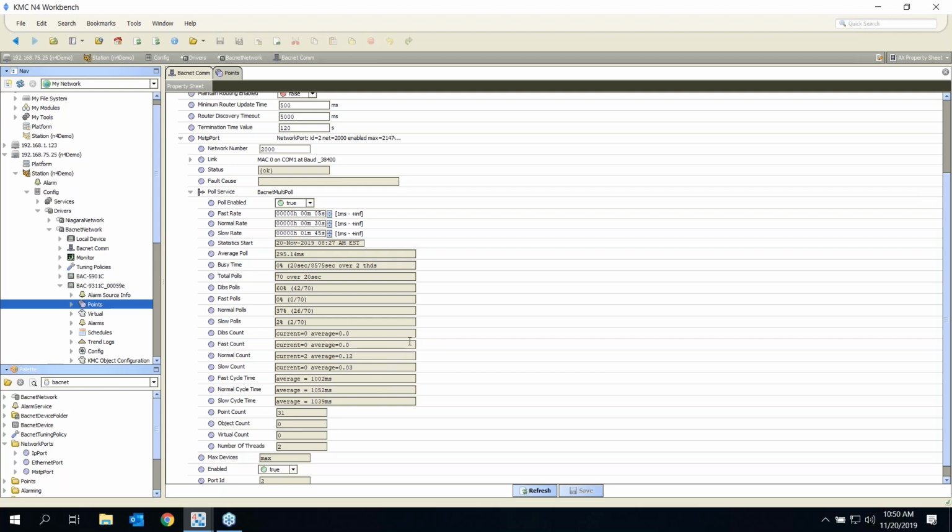When would a point stay subscribed and in the point count? If we have something like an alarm extension, a history extension, a control extension, or we've linked it to wire sheet logic or things of that nature, that's going to put the point into a permanently subscribed state, and it'll always be polled by the driver then. And that's really going to define your base number of points that are always being polled by the driver, even if no one's looking at the system.